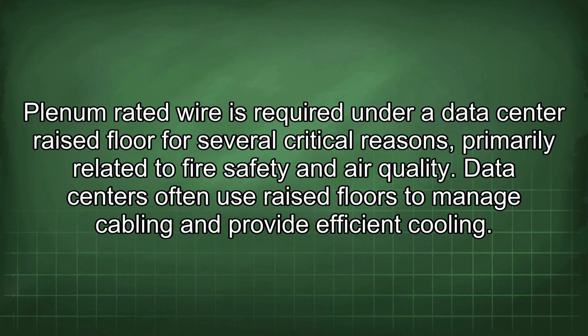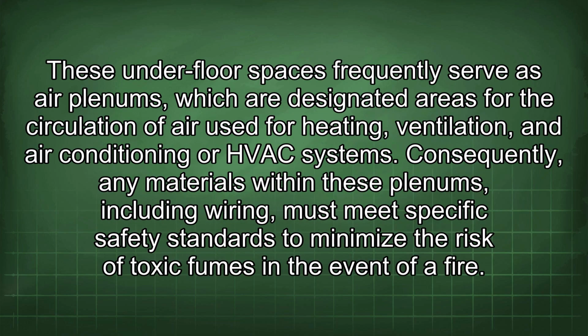Plenum-rated wire is required under a data center raised floor for several critical reasons, primarily related to fire safety and air quality. Data centers often use raised floors to manage cabling and provide efficient cooling. These underfloor spaces frequently serve as air plenums, which are designated areas for the circulation of air used for heating, ventilation, and air conditioning, or HVAC systems. Consequently, any materials within these plenums, including wiring, must meet specific safety standards to minimize the risk of toxic fumes in the event of a fire.